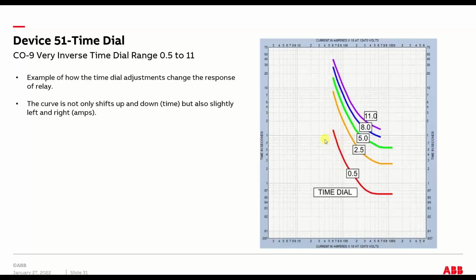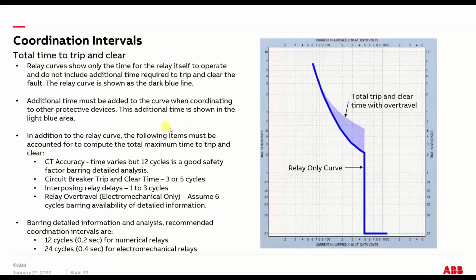And that's a little bit different than the way low voltage breakers with electronic trips work. Try to wrap it up here. This one's kind of important, so I'll go through it. The relay, and the curves that get represented in EasyPower and every standardized tool, is just the response of the relay, but it doesn't include what the breaker's doing.